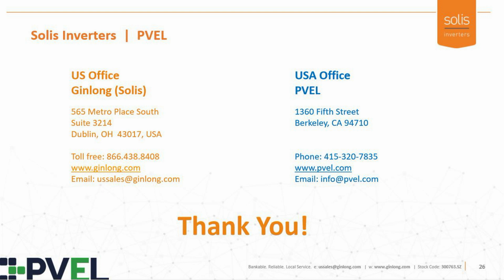The first part asks about UL 1741 certificate or IEEE 1547, and the standard for volt-var. So we do allow volt-var: on the 125 we allow daytime volt-var, and on the 255 we've also enabled nighttime volt-var, so you'll be able to adjust volt-var as needed during nighttime. That's a plus. In terms of daytime volt-var, the inverter is fully capable of 0.8 to 0.8 lead-lag volt-var.